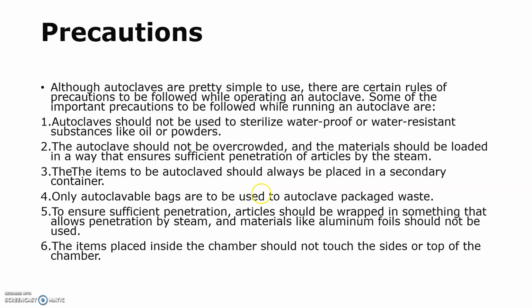Autoclaves should not be used to sterilize waterproof or water-resistant substances like oil or powders. For these, we recommend dry heat sterilization or a hot air oven. The autoclave should not be overcrowded. The material should be loaded in a way which ensures sufficient penetration of articles by the steam. The items to be autoclaved should always be packed in a secondary container. Only autoclavable bags are to be used to autoclave packaged waste. To ensure sufficient penetration, articles should be wrapped in something that allows the penetration of heat, and materials like aluminium foil should not be used.